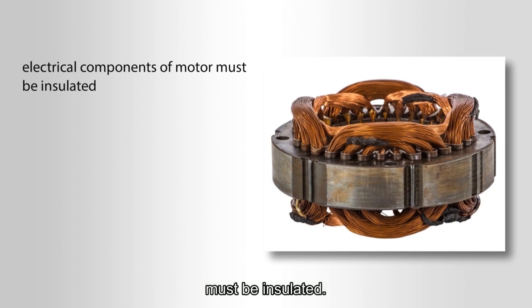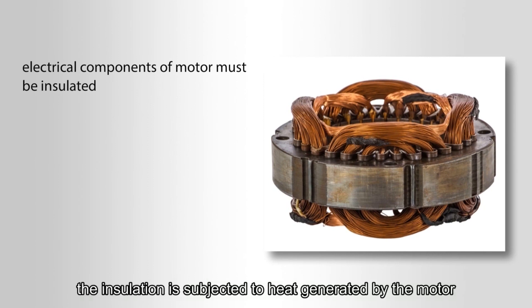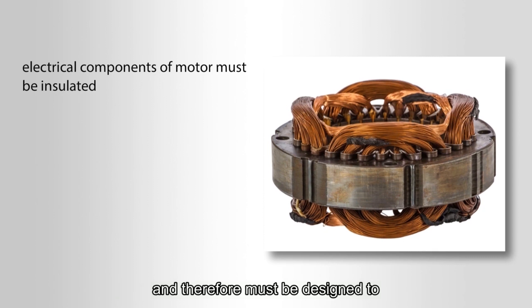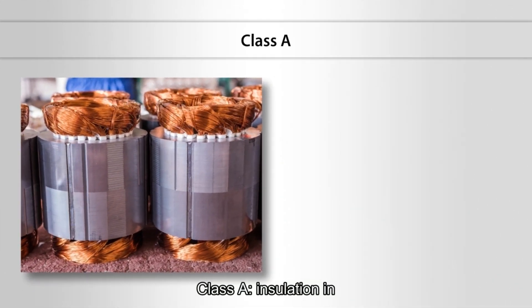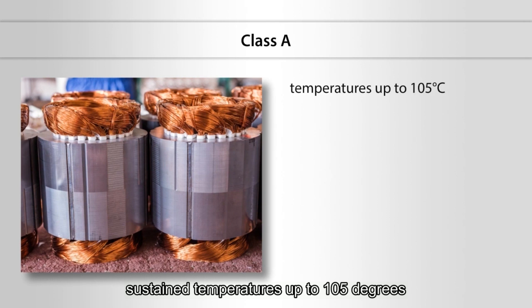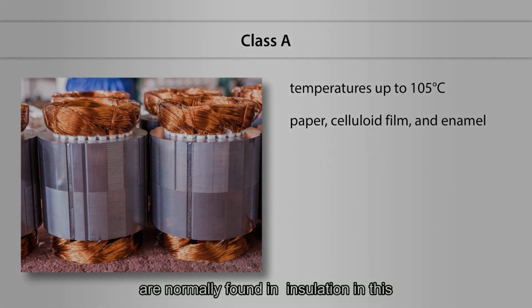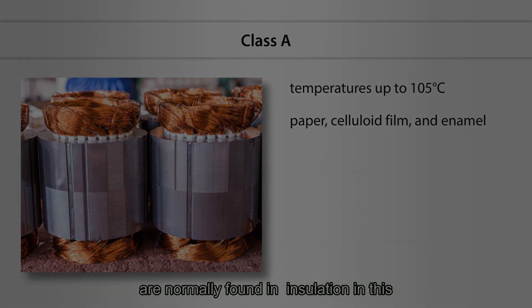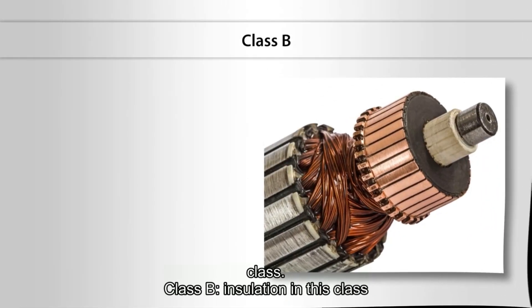The electrical components of a motor must be insulated. The insulation is subjected to heat generated by the motor and therefore must be designed to withstand the heat generated in a specific application. Class A insulation: in this class, insulation must be suitable for sustained temperatures up to 105 degrees Celsius. Paper, celluloid film, and enamel are normally found in insulation in this class.